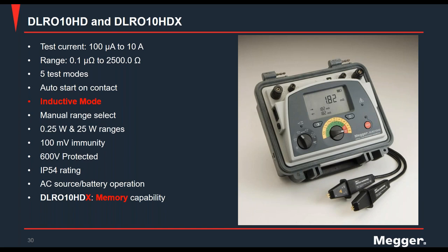You have the 0.25 watt and the 25 watt ranges. Not all test specimens can have the same power applied to them to make measurements, right? You can have a printed circuit board that's going to have a different dissipation or different amount of power you can subject it to versus a circuit breaker. So that's why you have these two modes.